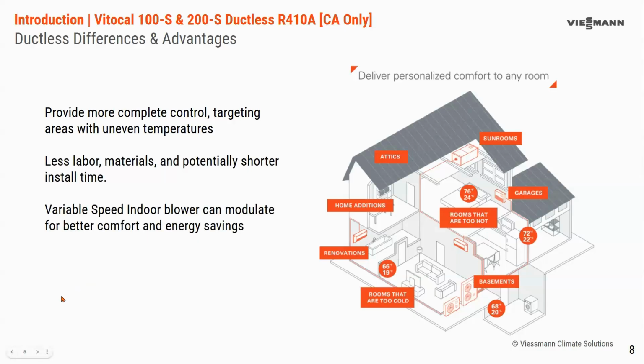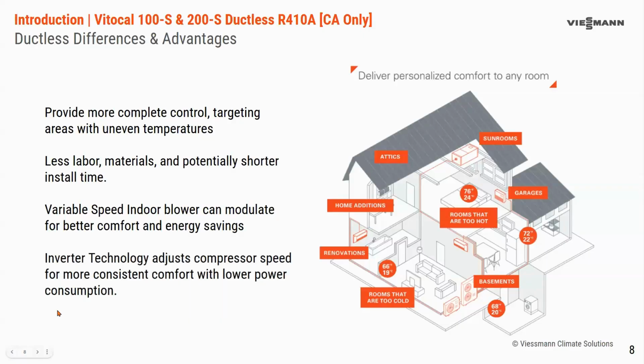Both the indoor unit and the outdoor unit have variable speed, both the motor and the compressor. That allows the system to modulate, to go back to that first point, to provide more consistent temperature control. Using feedback from sensors, the system is able to exactly meet the demand and provide heating or cooling in spaces that were previously unconditioned, or were uncomfortable due to their location or the ductwork run to that location. So you're able to now bring comfort essentially anywhere.